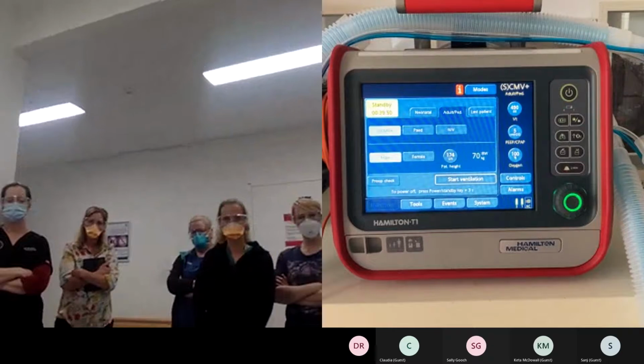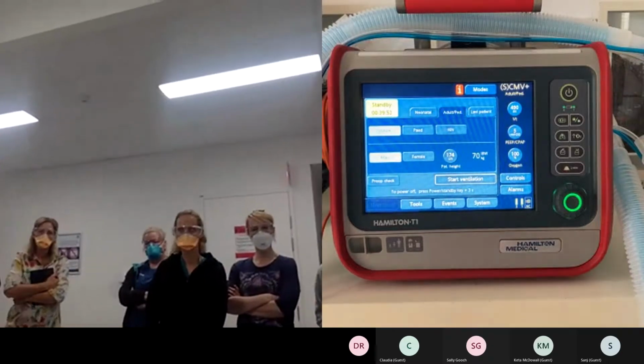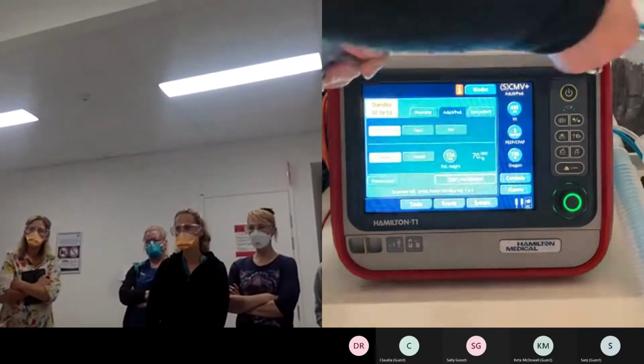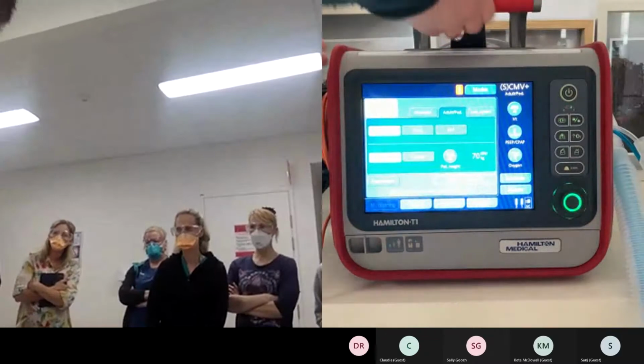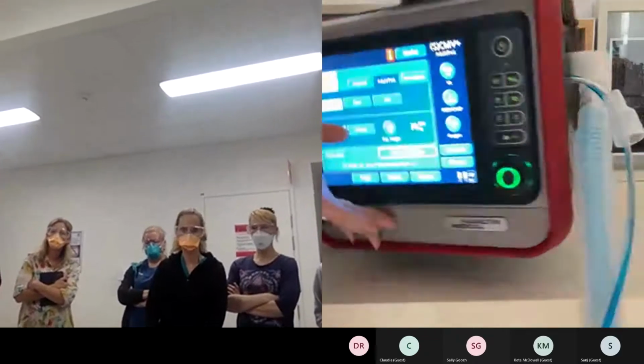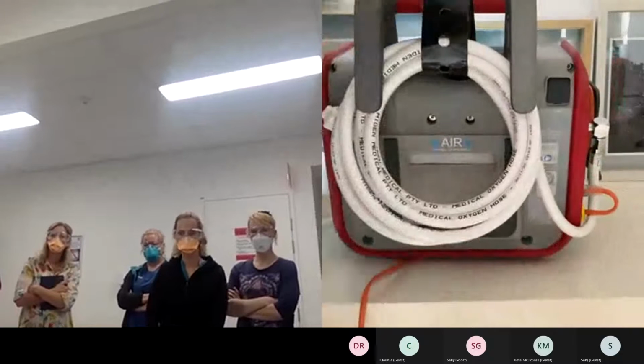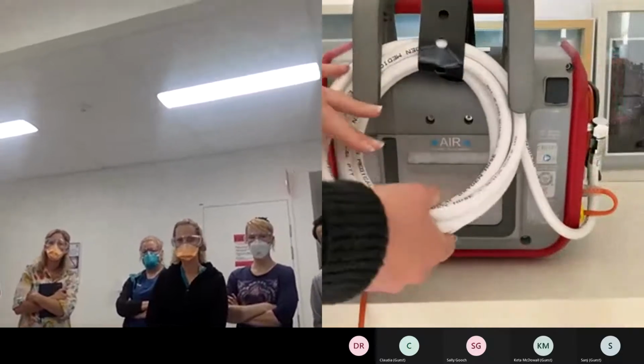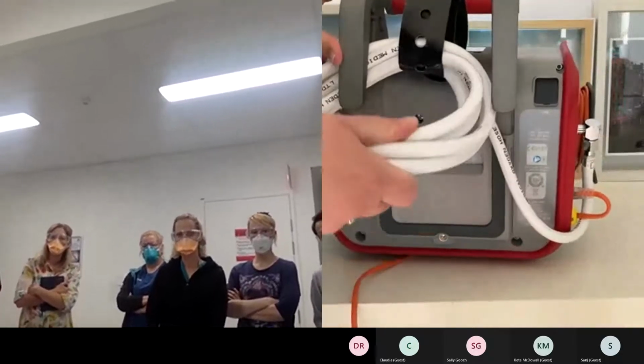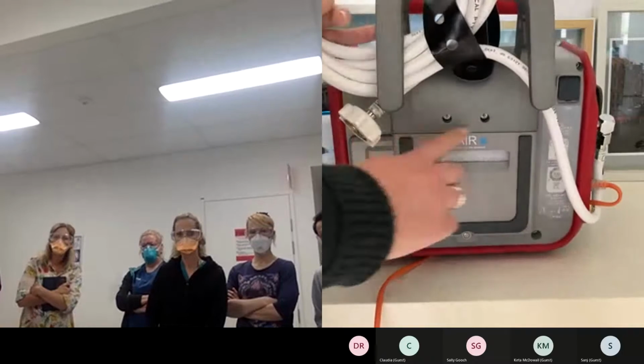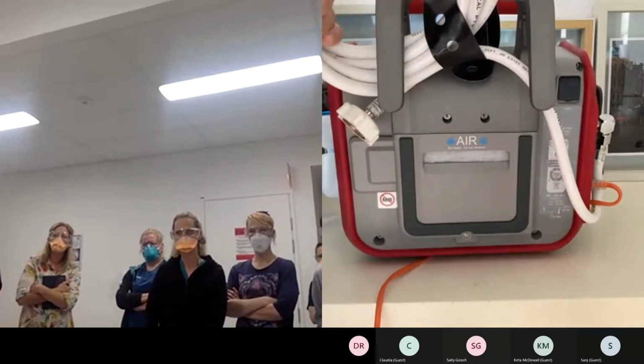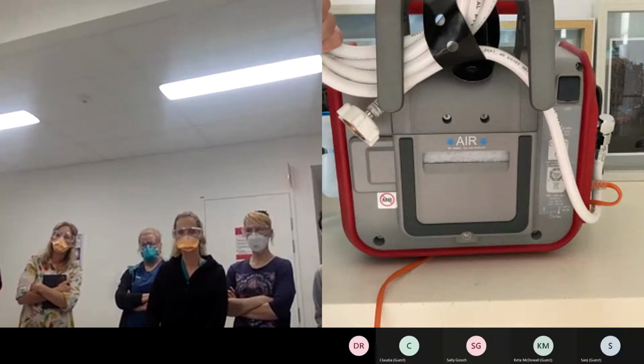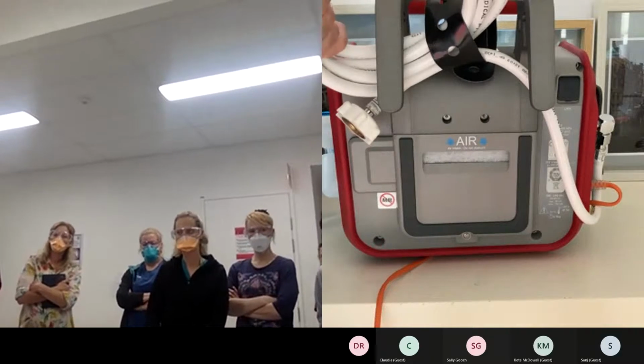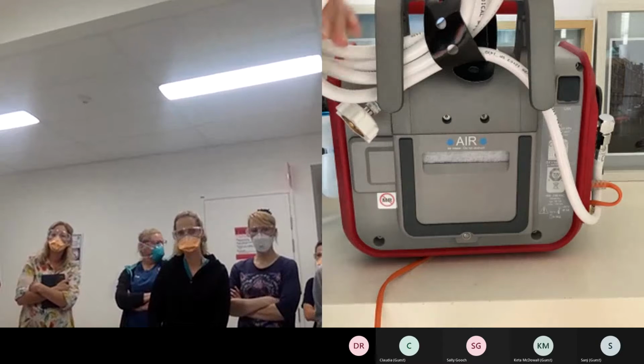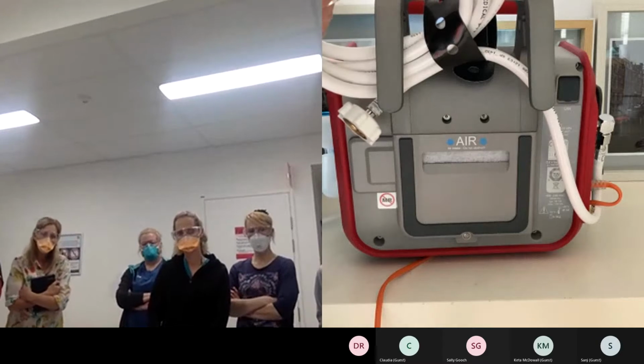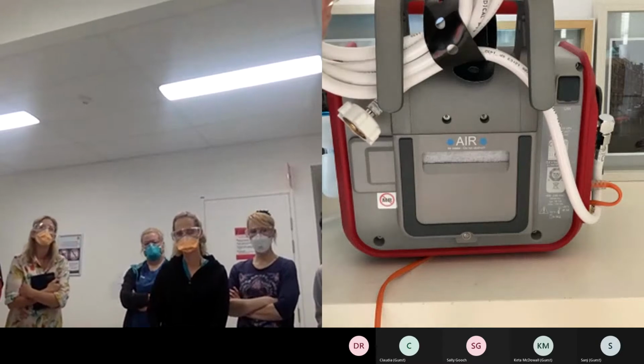Okay, so just when you look at the back of the machine, the Hamiltons are turbine driven. What that means is that they've got the ability to entrain air through their back port. So there's this little port in the back where it's going to pull air into the machine. So you don't have an external air supply. You've only got an oxygen hose. So it means that if your oxygen ever runs out, it's still going to deliver breaths in 21%.